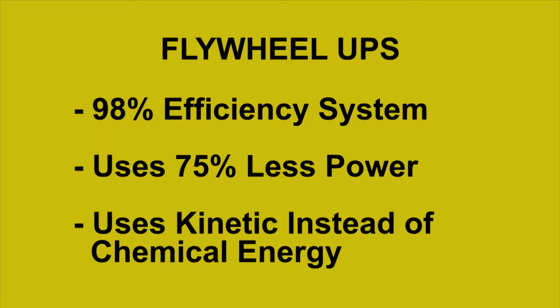Usable power typically lasts 15 to 60 seconds and acts as a bridge to ride through the period that it takes to bring the emergency power source online. The UPS system that Alban CAT provides is a 98% high efficiency system and uses about a quarter of the power that it takes to run its battery counterpart. Let's take a look at our 900 kVA UPS system.